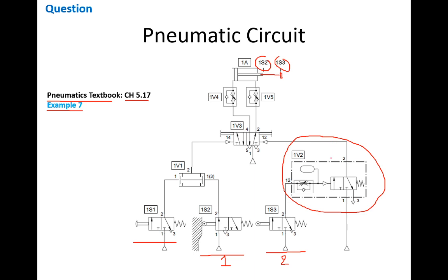If this time valve has been set to 5 seconds delay, then the piston will stay extended for 5 seconds, and only then retract to its initial position. To activate this time valve we are using limit switch 1S3, which is the second limit switch. The DCV is double pilot.